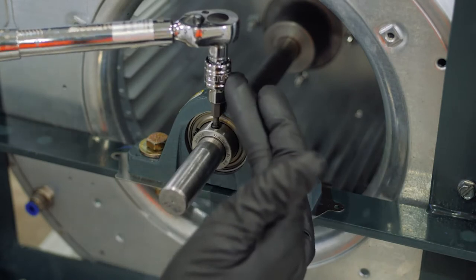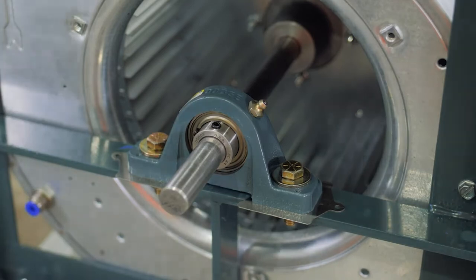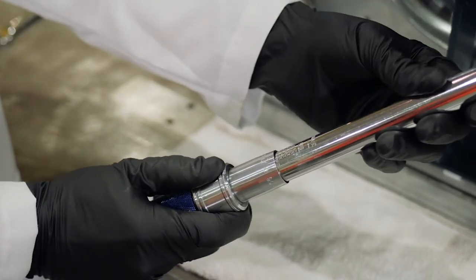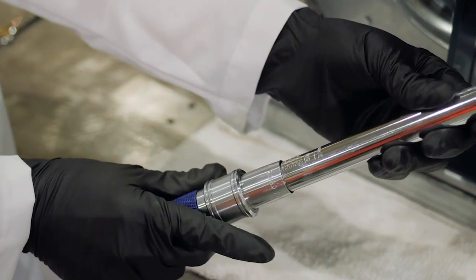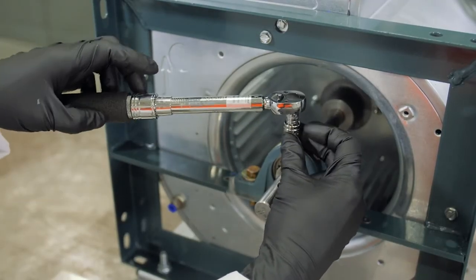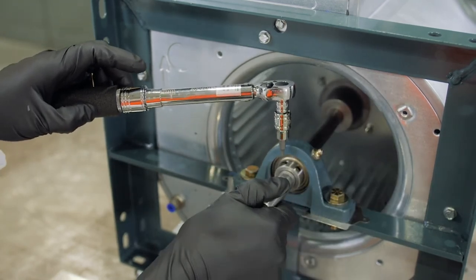Tighten both set screws until resistance is encountered. Next, using a torque wrench, alternate tightening set screws in small increments until reaching the torque value specified in the instruction manual. After 24 hours of operation, retighten set screws using the same procedure to ensure full locking of the bearing to the shaft.